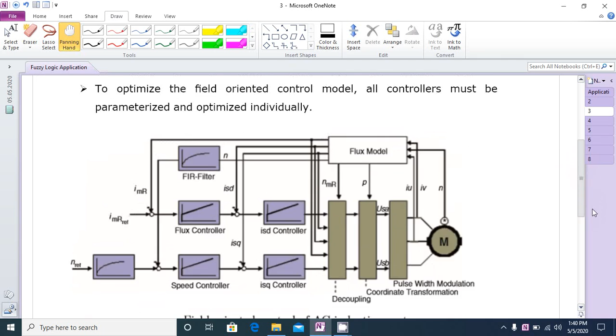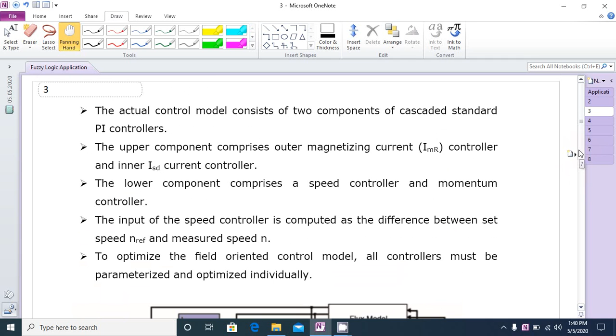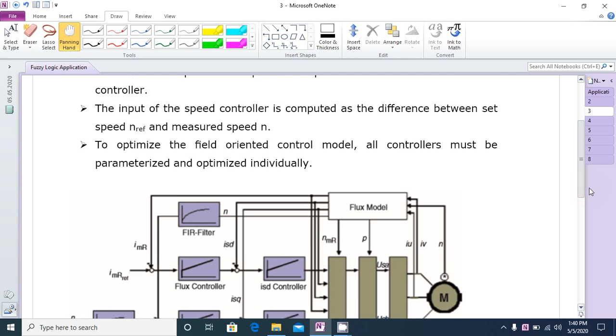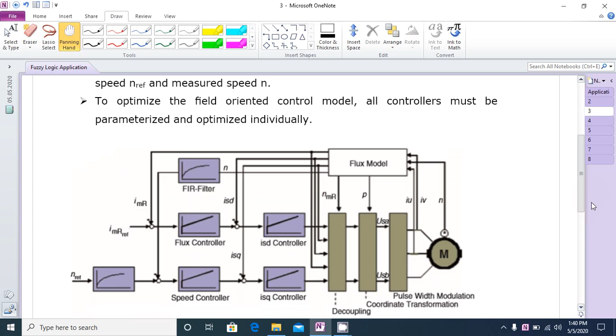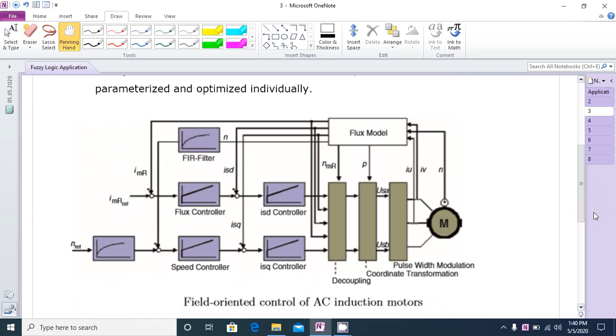In this, the actual controller consists of two components, which are cascaded standard PI controllers. The upper component comprises an outer magnetizing current controller and an inner stator direct axis current controller. The lower component comprises a speed controller and a momentum controller. The input of the speed controller is computed as the difference between set speed and measured speed. To optimize the field-oriented control model, all controllers must be parameterized and optimized individually. See the figure of field-oriented control of AC induction motor.